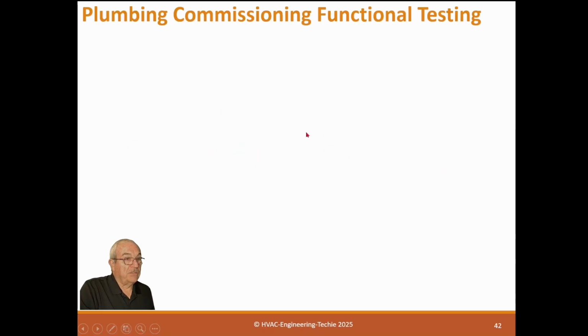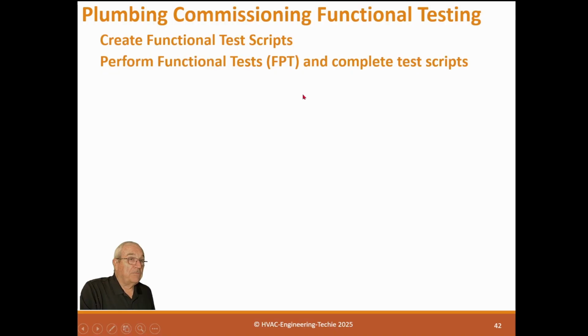So, plumbing commissioning after construction: create functional test scripts and perform functional tests. Now remember, the functional test is always critical scope because it's on the critical path for a construction job. Functional tests have to be done once the job is 100% complete. It doesn't have to have all the painting touch-up done. That doesn't matter. What does matter is that the craft you're in is 100% complete, and the test needs to be prior to occupancy. So that's why it's critical path. It needs to be right in that performance.